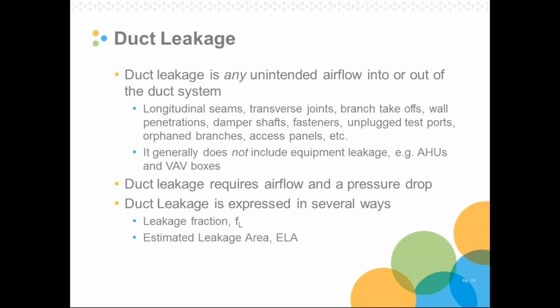We talk about duct leakage, at least in the literature, in several different ways. Two of the most common are the leakage fraction and estimated leakage area. The leakage fraction is essentially just the fraction of air of the total flow rate that doesn't make it to the outlet of the system. So if you have, again, our 1,000 CFM system with 10% leakage, we're leaking 100 CFM out of that system before it reaches the final termination. Estimated leakage area tries to estimate the total area of the leaks in the system. So this gives you an impression of how big maybe one giant hole would be to have to leak that much air. So again, returning to our 1,000 CFM example, we might have leaks that add up to about 10 square inches to leak our 10% of air, or 100 CFM.